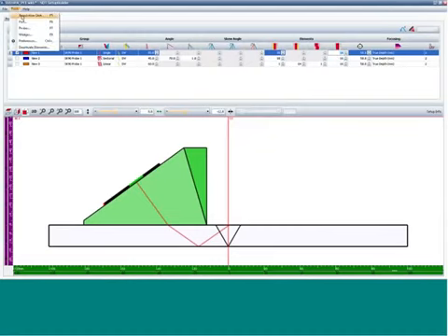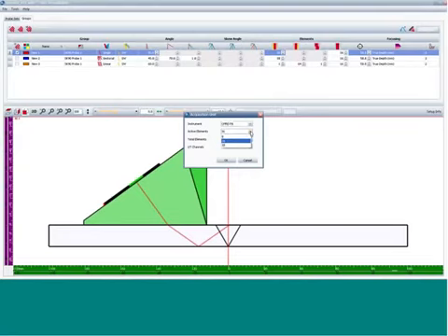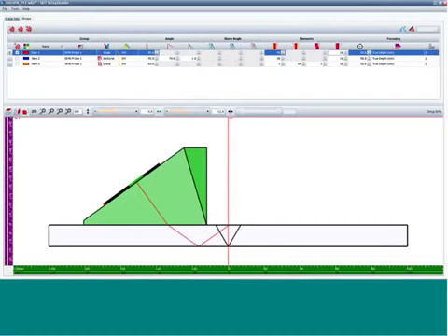Were I using an acquisition unit with more capacity, then I would have the ability to use more elements. So I have a focus distance here of 50 millimeters in true depth. One static focal law group.